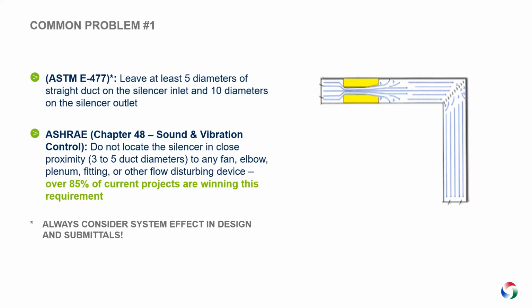And based on this ASTM E477 testing requirements, we have to leave 5 diameters of straight duct at the silencer inlet and 10 diameters of straight duct at the silencer outlet. So whenever you see a noise control manufacturer showing the pressure drop, it will always be the ideal pressure drop, and that's how it is calculated in the labs.